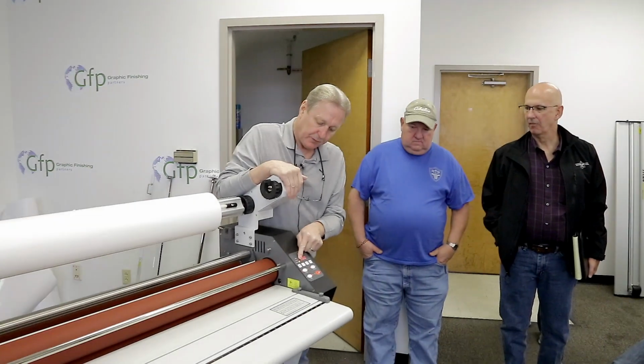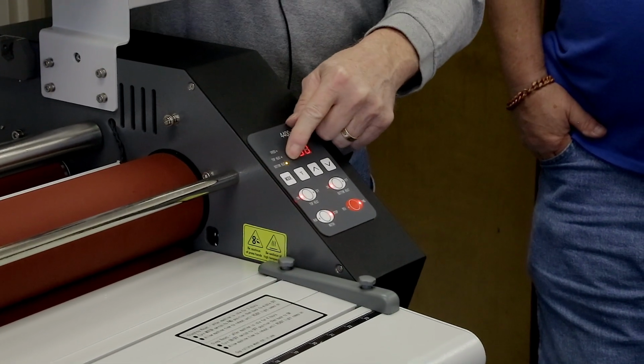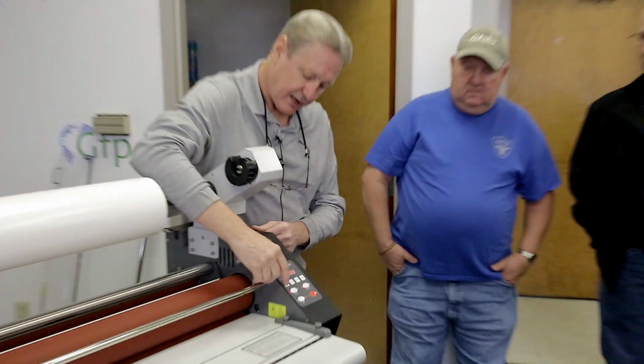When it's heating up, the light flashes. Remember, I didn't have the bottom heat on, so you can see it's flashing. If I go back to the top, it's constant because we're at our set temperature. Now I believe, and I've got to go back through the program, if I go way over my set temperature, that gives us a different error code. On some of them, like on the 2700s, if you go over a certain temperature, the light starts flashing really fast. That tells you that you're higher than your set temperature and out of spec. What would normally cause that is a blocked sensor. But we changed the program to warn you now. If a sensor gets blocked, it tells you, I'm blocked. Clean out the blockage, and then we'll start over.